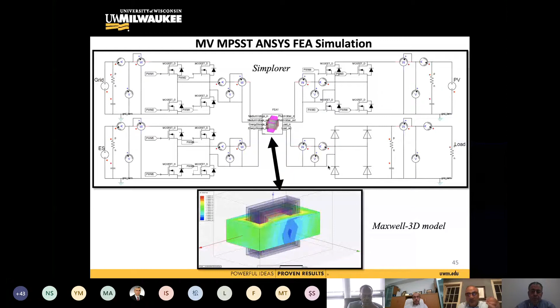So for that, you really need to do another level of optimization to consider switching loss and transformer loss. One way to do it is to simulate the system with actual parameters. We take our transformer, design it, take it to a Maxwell 3D model, then bring it as a co-simulation to Simplorer. We apply the switching, and in this model you can look at the transformer loss, the switching loss, and all the conduction loss. In addition, you can look at all the transients and what happens to your flux, and whether you get saturation or not. This is a really good way of optimizing your system, and it comes almost as the last step after you do all your design work.